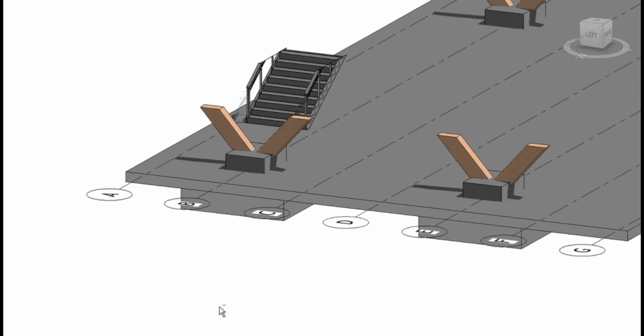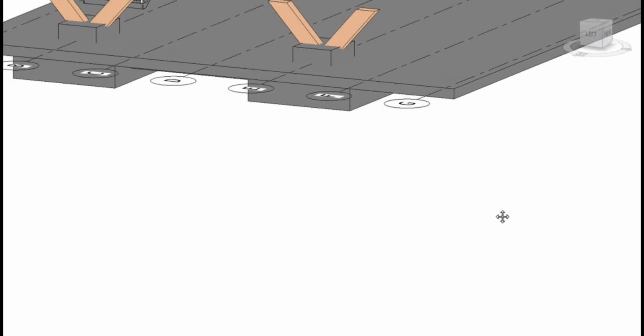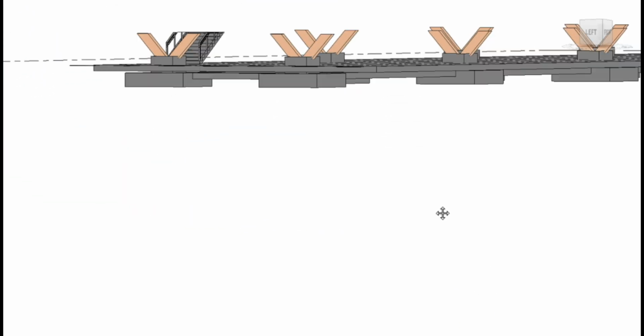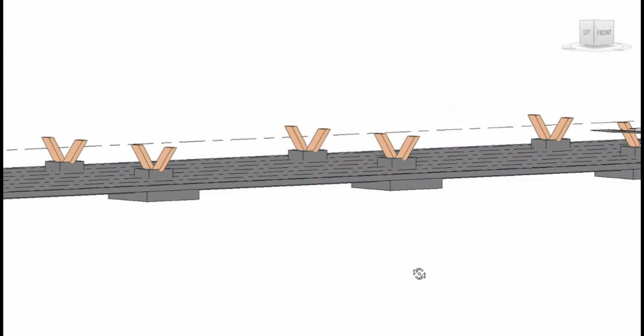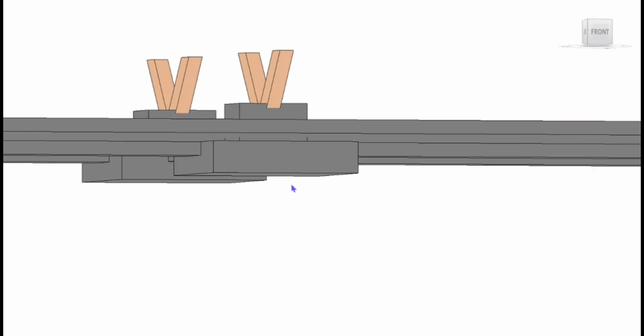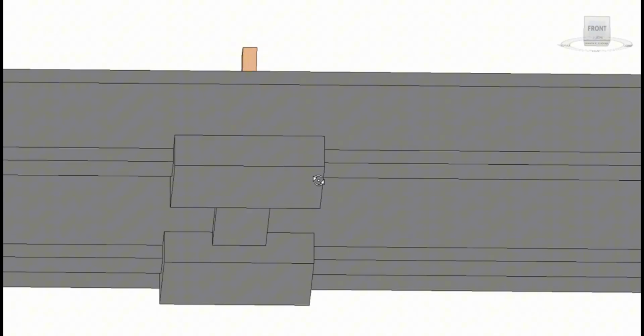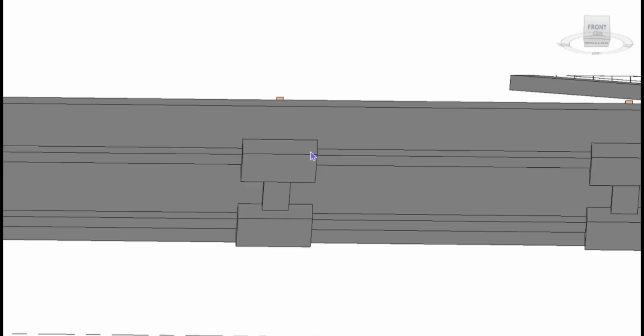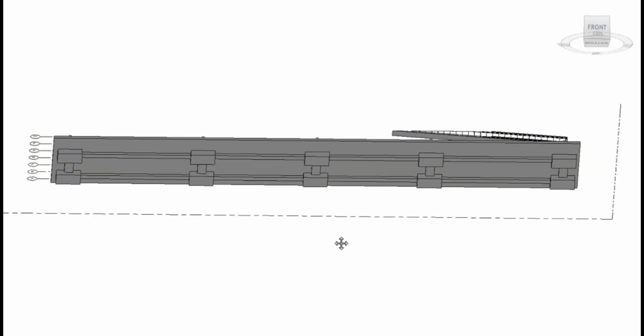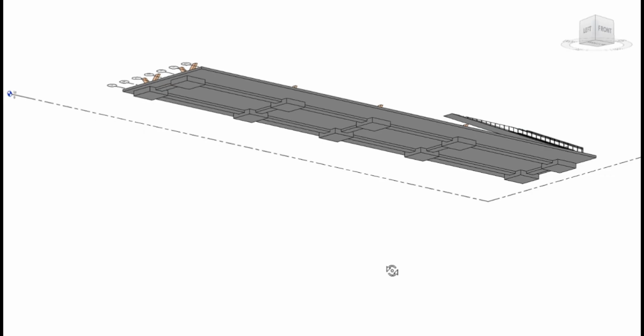Each V-frame sits on a combined footing sized from an allowable soil-bearing capacity of 200 kilonewtons per square meter, with a pre-sizing of a 3.16 by 3.16 face and 0.70 meter thickness. Tie beams link the footings and manage any horizontal thrust from the V-legs.